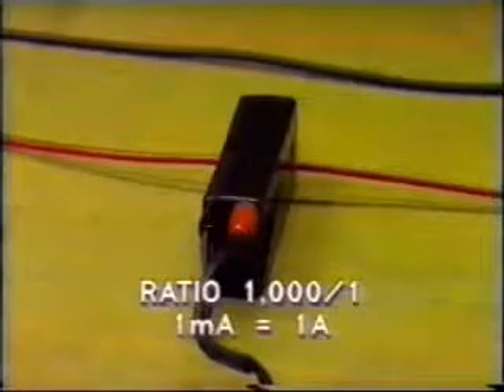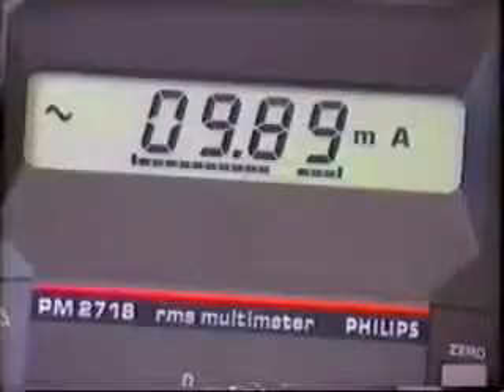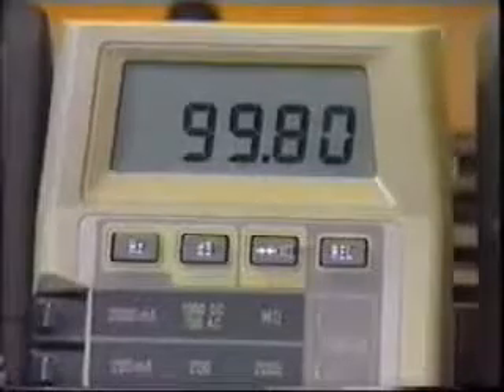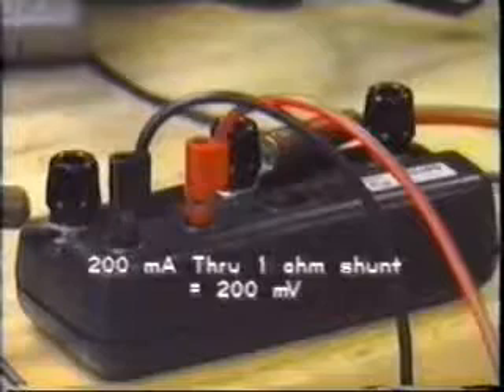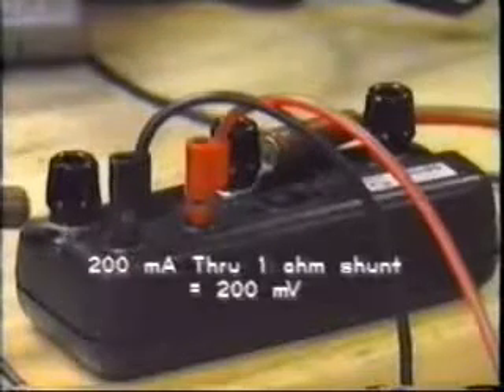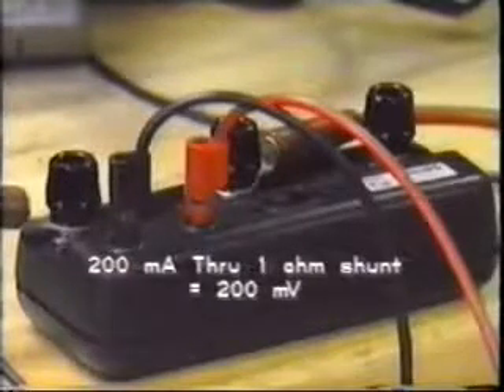One type of probe consists of a CT, usually wound with a convenient ratio of 1,000 to 1, so that 1 milliamp responds to 1 amp on the circuit being measured. The output can be measured by a multimeter or a millivoltmeter with a suitable shunt. For example, 200 milliamps through a 1 ohm shunt would give us a reading of 200 millivolts.